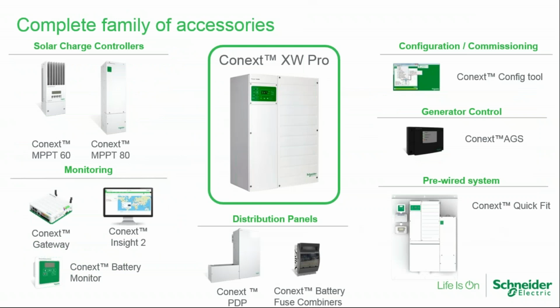So this is all the different stuff. We have charge controllers, a 60 amp 150 volt, and an 80 amp 600 volt for MPPT charging. We have monitoring, which is the gateway, along with the battery monitor. The interesting thing about the monitor is that it doesn't give you the granularity of the EMS in the battery. It gives you a battery bank capability, but it gives you state of charge, and it's a very accurate state of charge, which once we get the state of charge implemented in all the devices, can be a very powerful tool in determining when to start generators, when to switch over to the grid for charging, a number of other things.